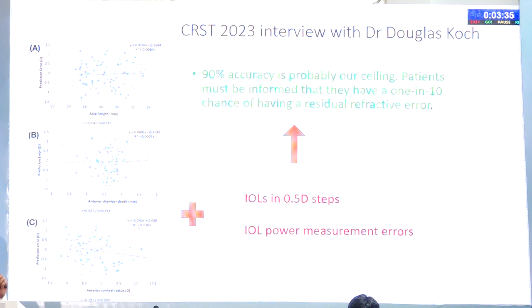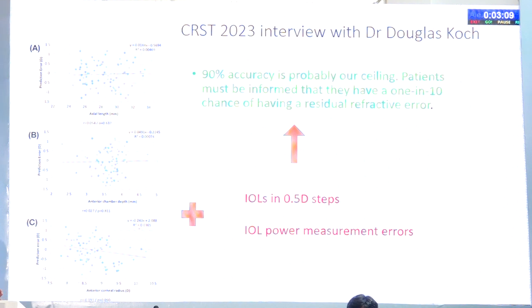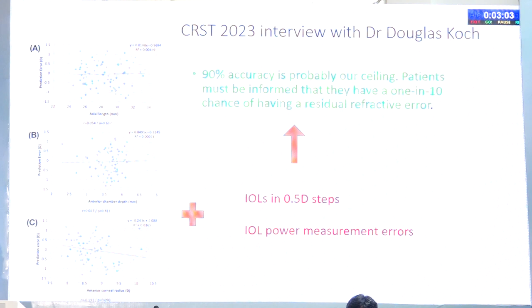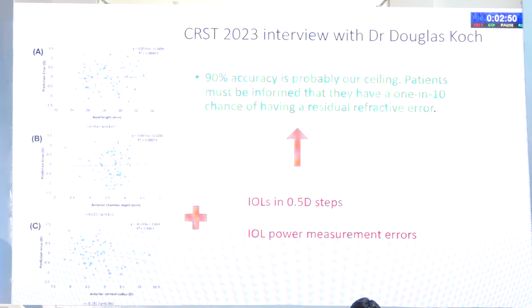Because IOLs come in 0.5-diopter steps and there are power measurement errors — a manufacturer's machine has an inbuilt measuring error of 0.18 standard deviation — a 0.2 diopter error exists at the manufacturer's end. These small errors of 0.1 or 0.2 can cancel each other or accumulate, and once in a while you will have a patient with an unusual refractive result. Douglas Koch in CRST 2023 said 90% accuracy is probably a ceiling given current technology, and patients must be informed they have a 1-in-10 chance of residual refractive error.